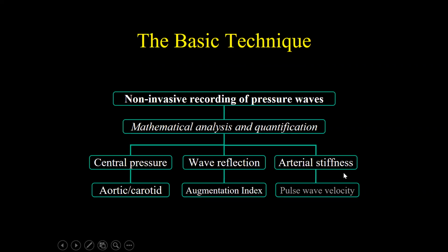And you can measure arterial stiffness in the form of arterial pulse wave velocity by gating the signal between a carotid measurement and a femoral measurement to the ECG, measuring the distance between them, and you'll then know how fast that pulse wave is traveling down the aorta. So fast transit time, a high pulse wave velocity, a stiff vessel.